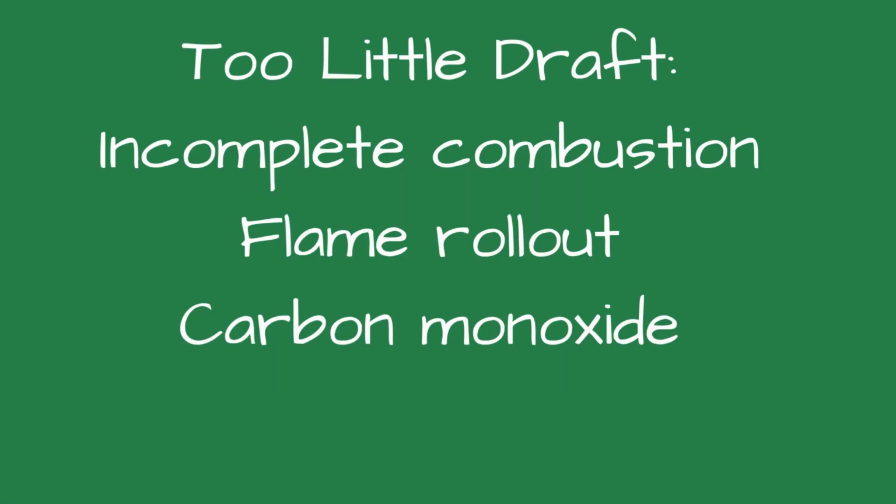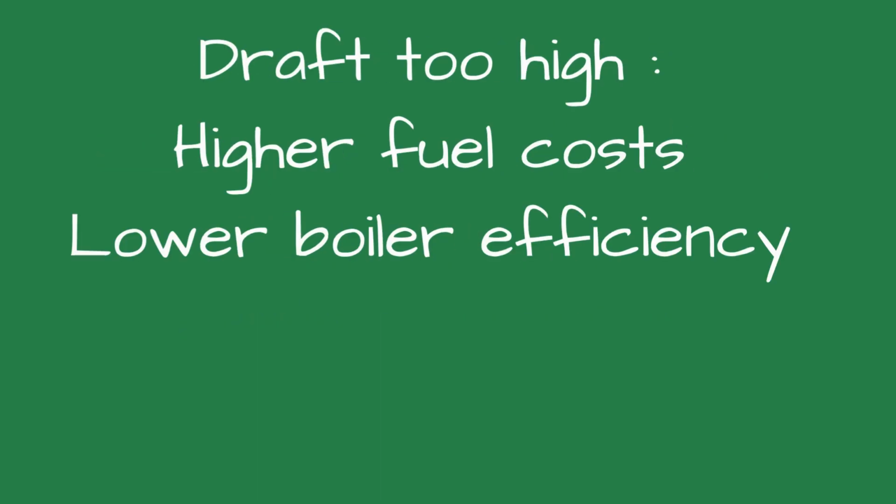Too little draft, the gases don't exit the combustion chamber fast enough. This leads to incomplete combustion, flame rollout, or even carbon monoxide buildup. Too much draft, this is like flushing your boiler's heat right up the chimney. The combustion gases whip through the boiler so fast that they don't transfer their heat to the water. You lose efficiency and money with every firing cycle.